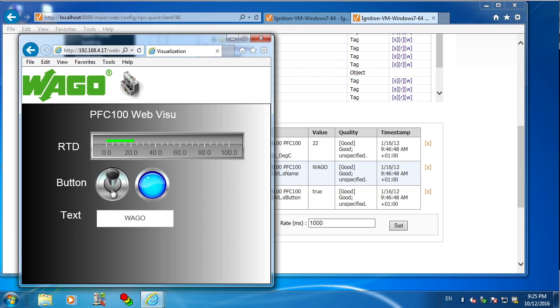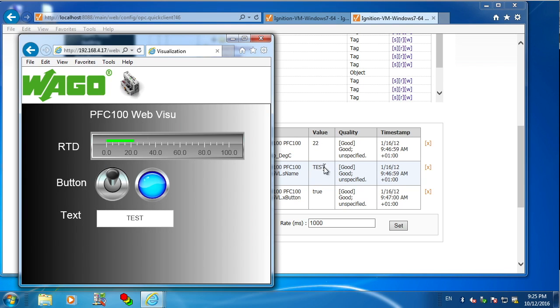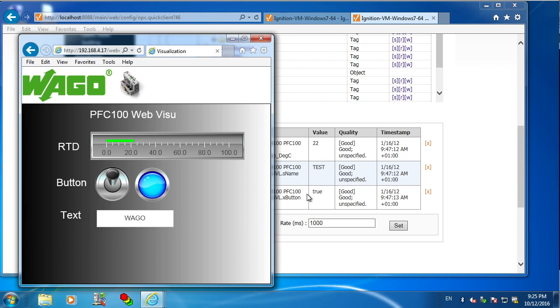So my boolean's working. I'll try a couple different text strings to see that string variables are handled by the OPC server as well. And it is.